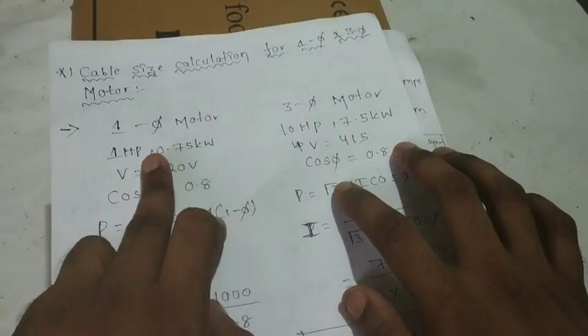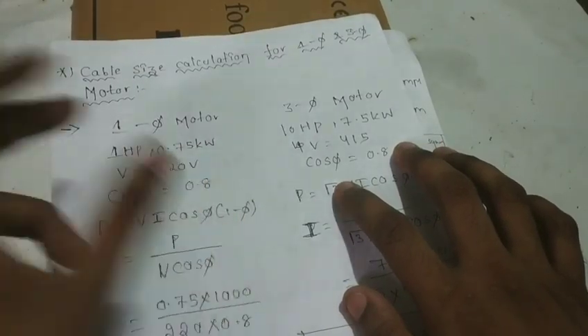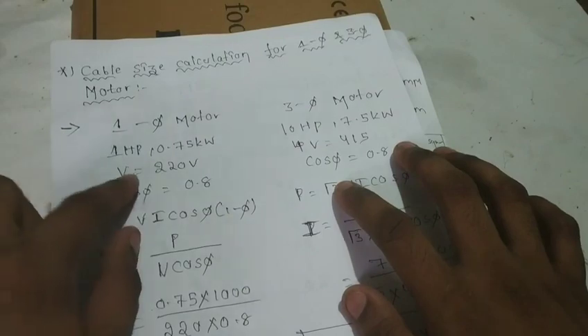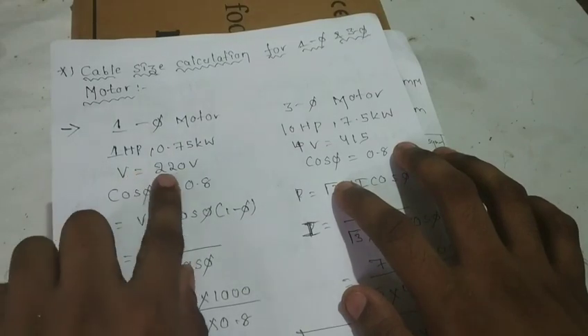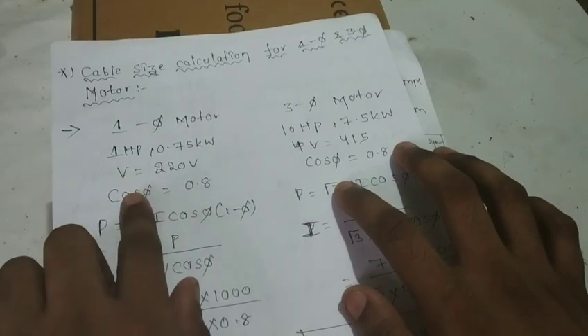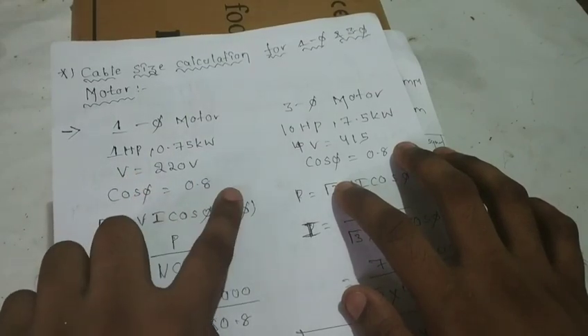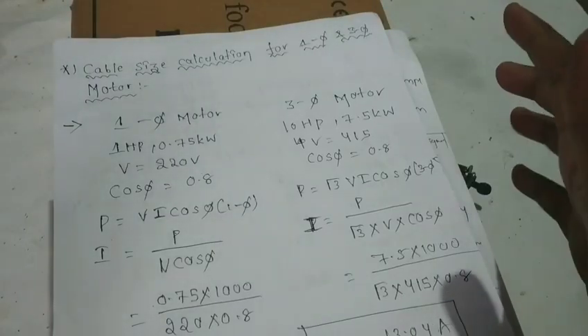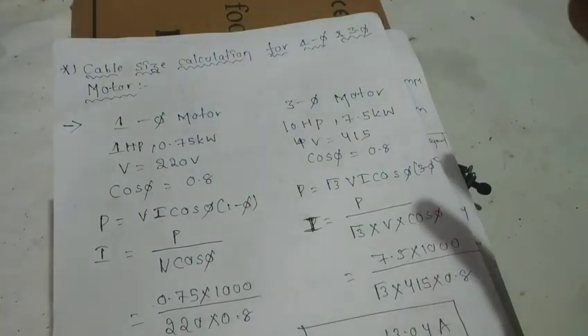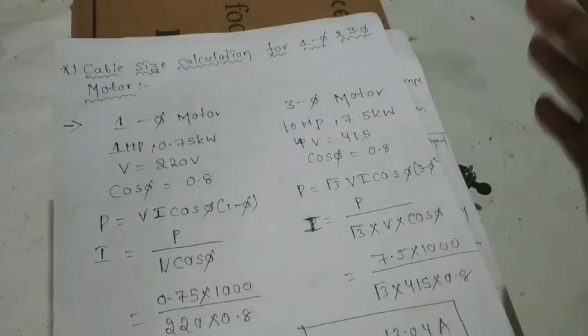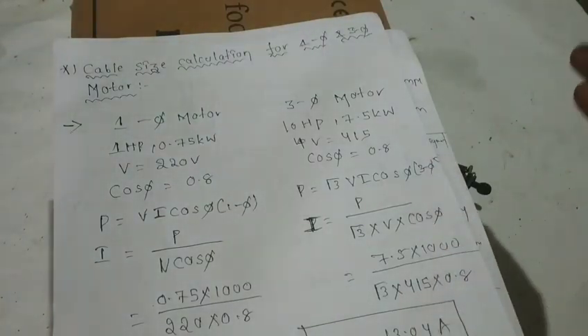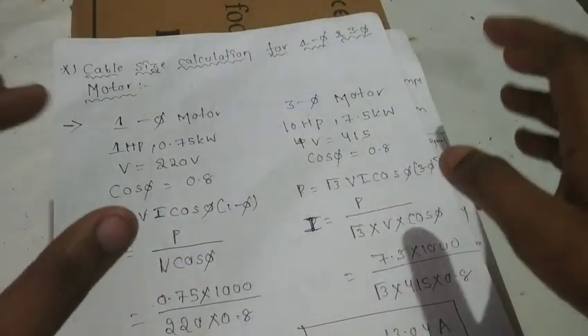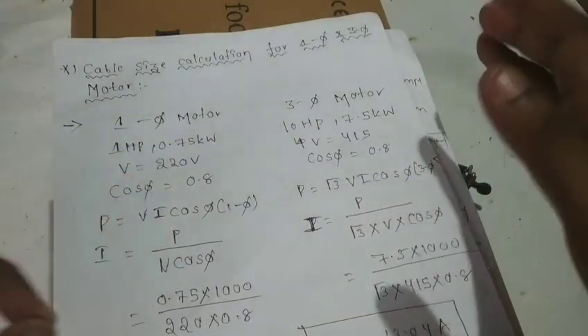The 1HP motor is 0.75kW. Voltage is 220V. The power factor cosφ is 0.8. We have to calculate using the formula P = V·I·cosφ. We have to calculate the current from this formula.